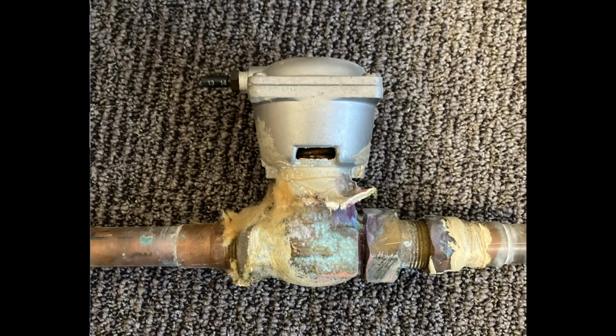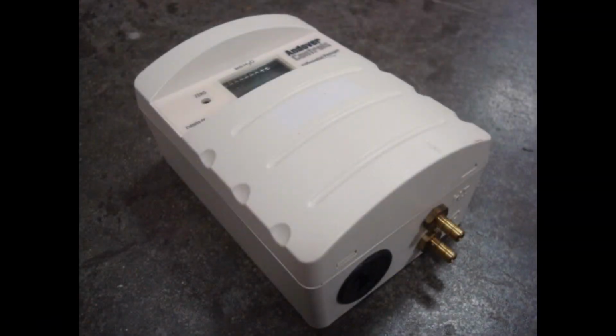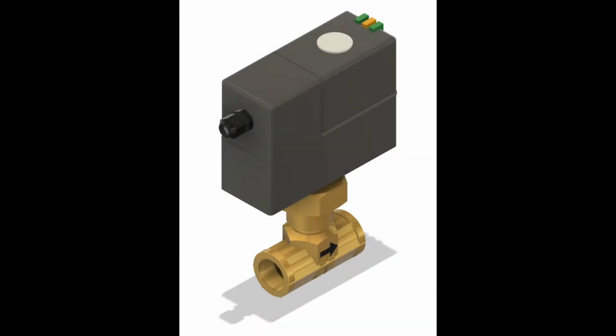So they also have these pneumatic options. We're replacing all of the pneumatic valves in our commercial office building with these electronic PIC valves. The problem with the pneumatics, you have to have a pressure transducer like this. You have to have air lines run all over your building. You have to maintain an air compressor just for the system. So these electronic PIC valves are much easier to manage and operate. Reduce overhead costs because you're not running an air compressor.